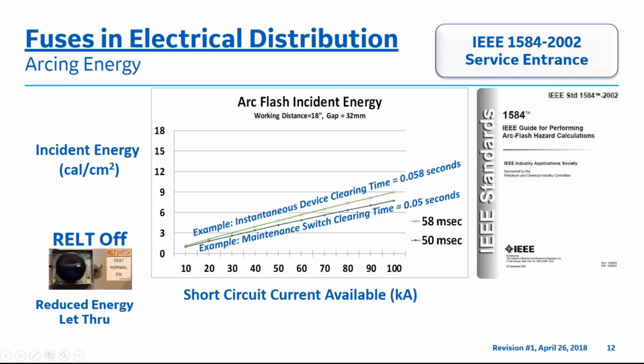This is an IEEE 1584 arc flash incident energy chart that utilizes the incident energy, calories per centimeter squared on the y-axis versus the short circuit current available on the x-axis. As you can see, there are two diagonal lines represented within the chart, such as at a low voltage service entrance application. The light green line drawn in that chart in the center is an instantaneous electronic device for fuses clearing at 0.058 seconds, or 58 milliseconds. The dark green line drawn in the center of the chart is a device with an electronic maintenance switch with a clearing time of 0.05 seconds, or 50 milliseconds.